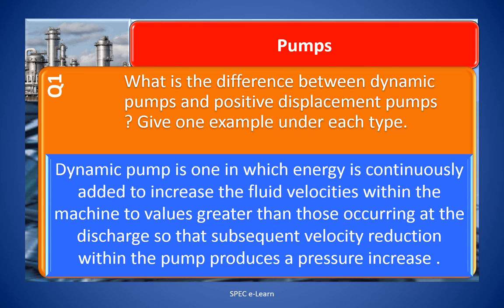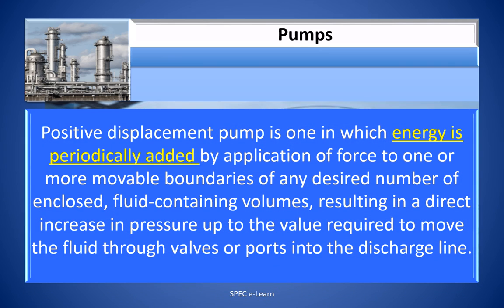The dynamic pump is one in which energy is continuously added to increase the fluid velocities within the machine to values greater than those occurring at the discharge, so that subsequent velocity reduction within the pump produces a pressure increase. Positive displacement pump is one in which energy is periodically added by application of force to one or more movable boundaries of any desired number of enclosed fluid-containing volumes, resulting in a direct increase in pressure up to the value required to move the fluid through the valves or ports into the discharge line.